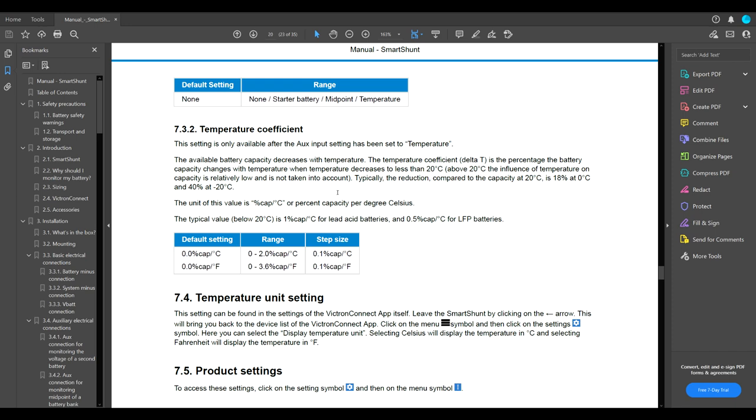What it says, the available battery capacity decreases with the temperature. The temperature coefficient is the percentage the battery capacity changes with the temperature when the temperature decreases to less than 20 degrees Celsius. Above 20 degrees Celsius, the influence of the temperature on capacity is relatively low and it's not taken into account. Typically, the reduction compared to the capacity at 20 degrees Celsius is 18% at 0 degrees Celsius and 40% at minus 20 degrees Celsius. We all know we're not going to be taking our lithium iron phosphate batteries below maybe negative 2, 3, if you have a really low discharge rate. But anyways, this is what it is.